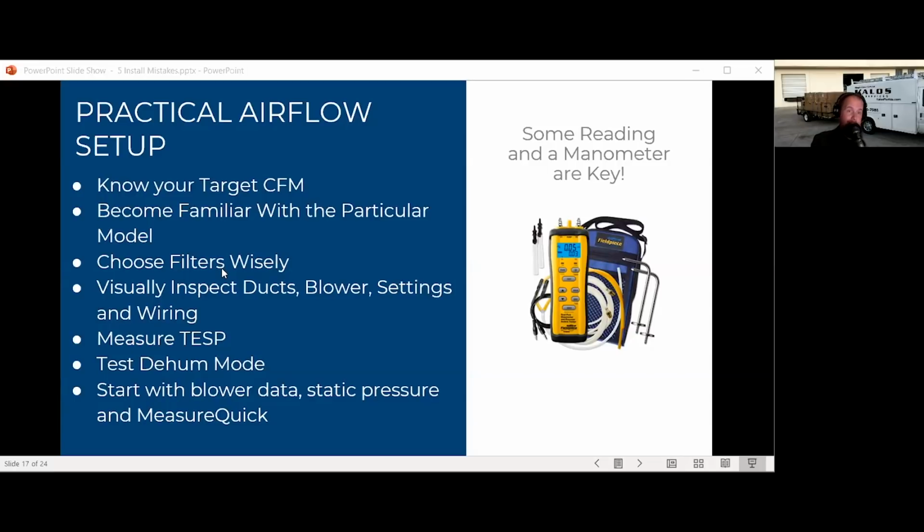Now that's a big if, right? And when it comes to validating airflow, purists would say, if you don't know exactly what it is, who's to say that control's set up properly? And it is true. But at that point, truly measuring air velocity for an installer is generally going to be over their head. If you have a true flow, that's actually the best way of doing it. And an installer can do that. Still just a touch mathy, depending on the manometer that you're doing it with. But true flow is probably the most practical way of doing that.